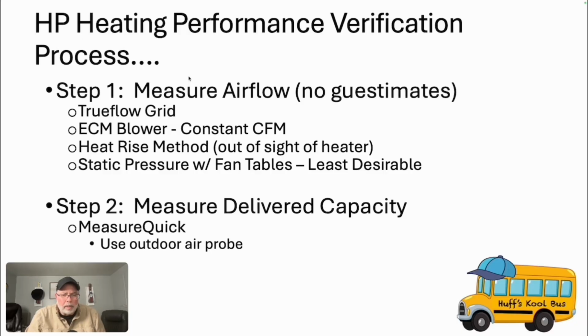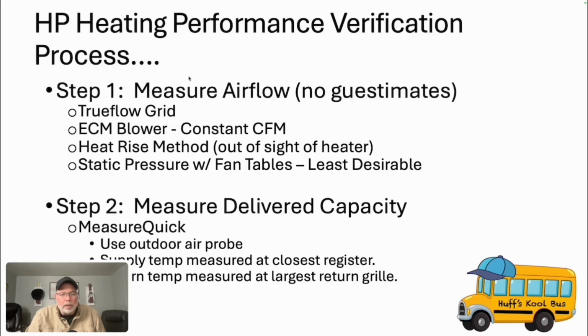Now, when you're using MeasureQuick, again, you want to use an outdoor air probe. In other words, don't be using WeatherBug, things like that. You actually want to be able to measure the outdoor air temperature right at or near the outdoor unit. Why? Well, if you use WeatherBug in my area, the weather station is about 14 miles away. And a lot of times my house can be 4, 5, 6 degrees colder than where that weather station is, just because of where I'm located up on the side of this mountain. So, you want the actual measured outdoor air temperature. You want to measure the supply temperature at the closest register, just like we talked about. And then you're going to take the return temperature at the largest return grill.